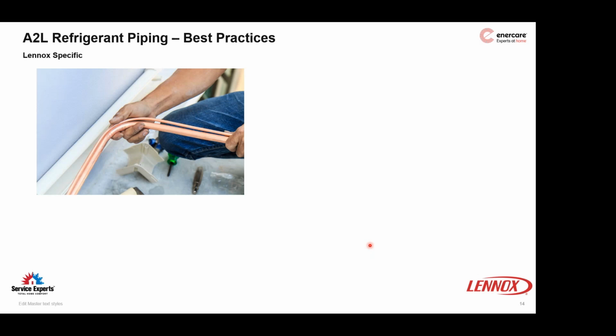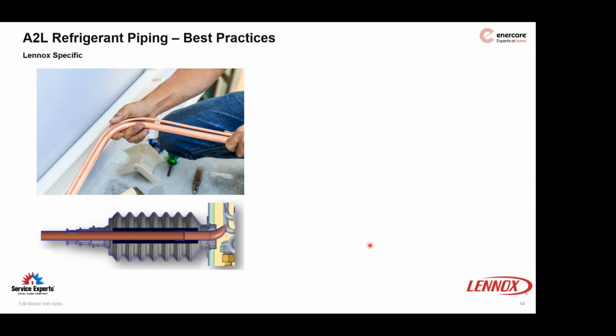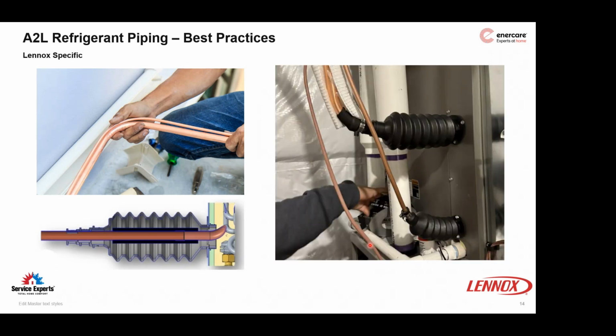Like I said, R32 makes up 70% of R454B, and it made up 50% of R410A. So we'll talk about a couple of the key differences that's coming, at least with Lennox anyway. Lennox now uses a pipe sleeve. You can see these pictured here at the 2 indoor joint connections.